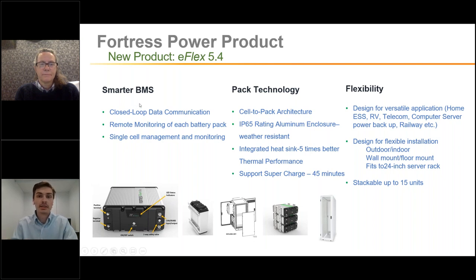The BMS in this is contactor-based or relay-based, which allows closed-loop data communication with different inverters. As of now, we have Solark, Schneider, and Outback confirmed with closed-loop communication. In a nutshell, this means the inverter and battery talk with one another seamlessly, with no manually inputting parameters. It's very easy and makes for a nice plug-and-play solution.